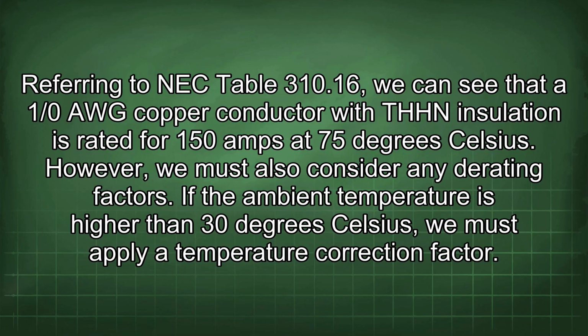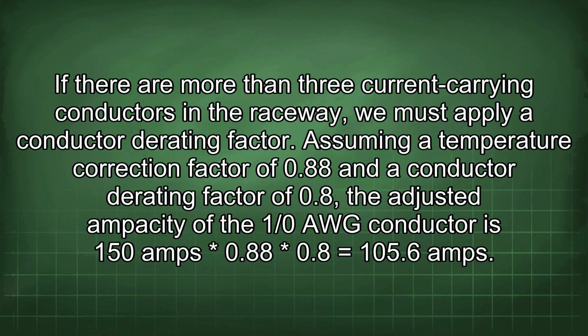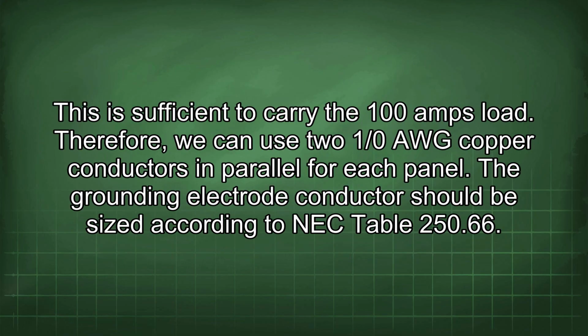However, we must also consider any derating factors. If the ambient temperature is higher than 30 degrees Celsius, we must apply a temperature correction factor. If there are more than 3 current carrying conductors in the raceway, we must apply a conductor derating factor. Assuming a temperature correction factor of 0.88 and a conductor derating factor of 0.8, the adjusted ampacity of the 1/0 AWG conductor is 150 amps * 0.88 * 0.8 equals 105.6 amps. This is sufficient to carry the 100 amps load. Therefore, we can use two 1/0 AWG copper conductors in parallel for each panel.